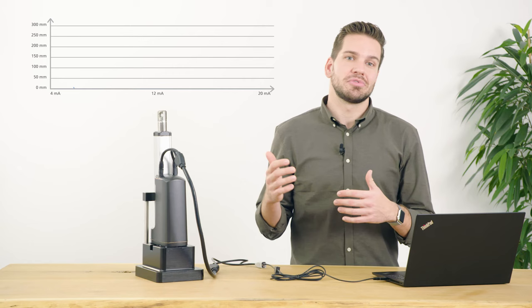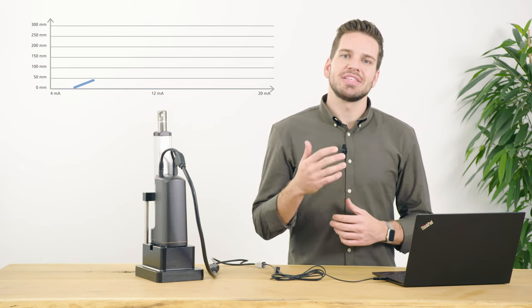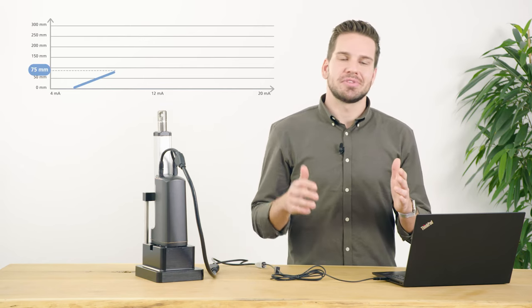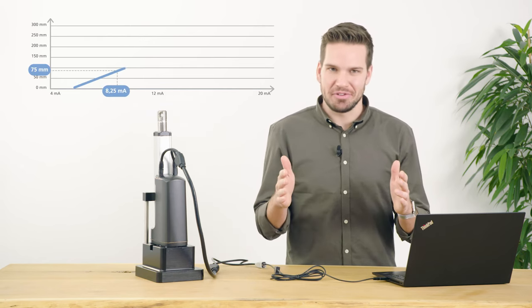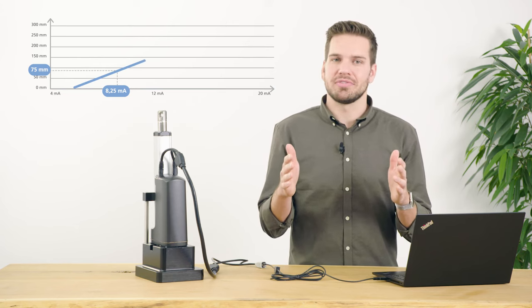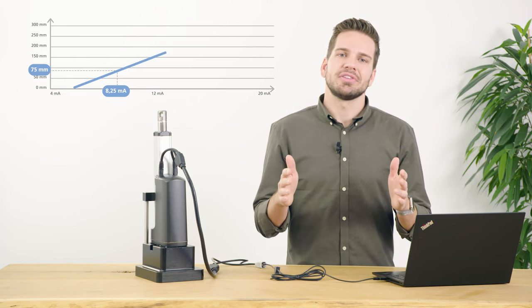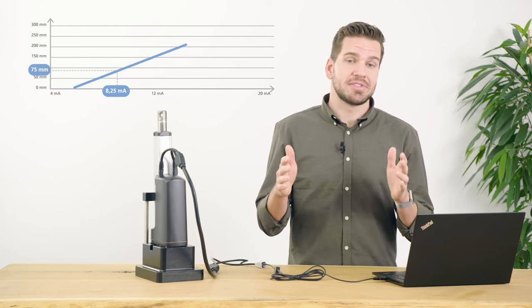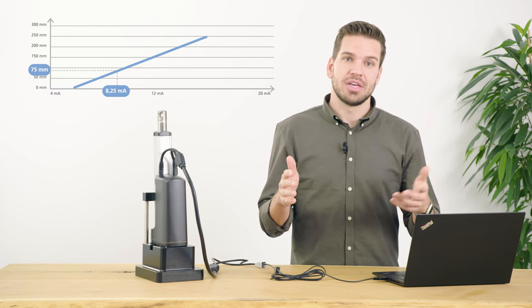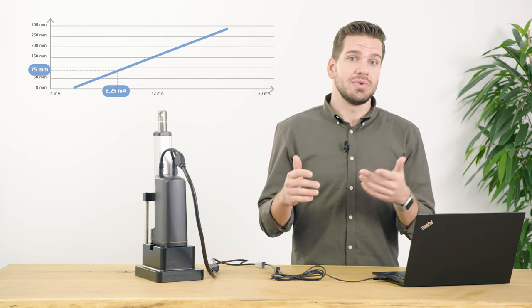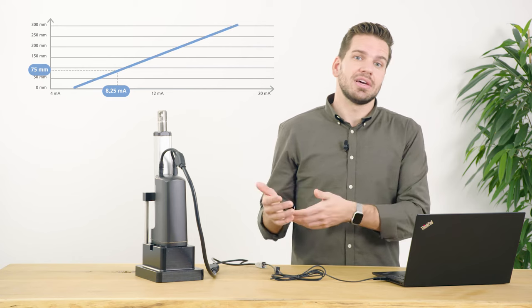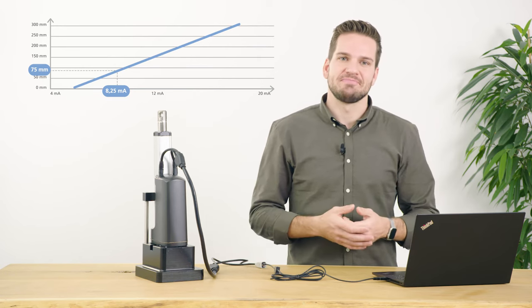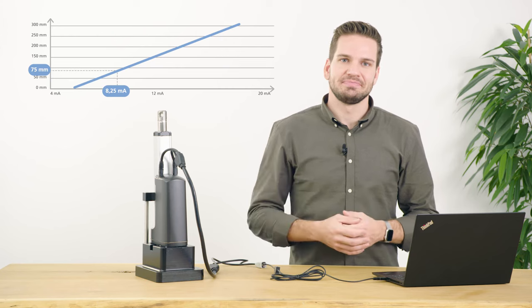Let's take an example of a 300 millimeter actuator with 4 to 20 milliamps servo control. You can run this actuator between 4.5 milliamps to 19.5 milliamps, equal to the stroke length of the actuator. There are two outer limits, which ensures that the actuator stops if the signal becomes too low, like a disconnected cable, or too high if the conductor is short-circuited to the VCC. This is visualized in the illustration here.